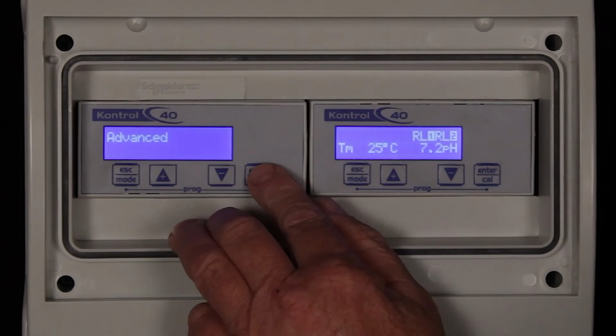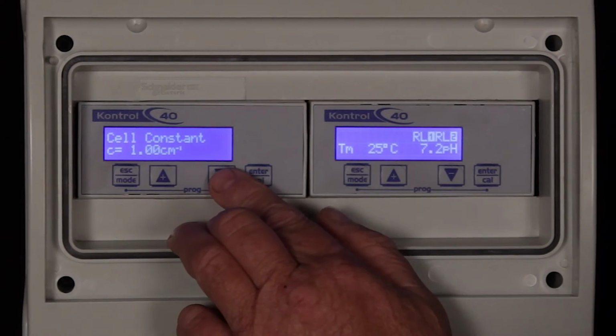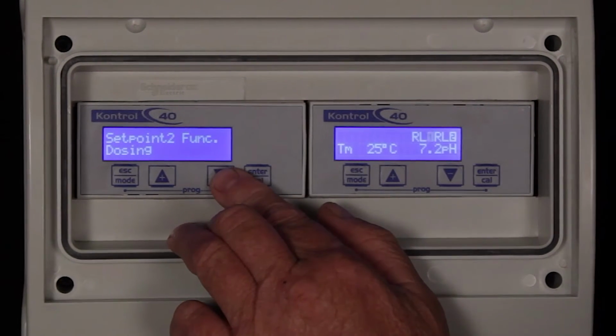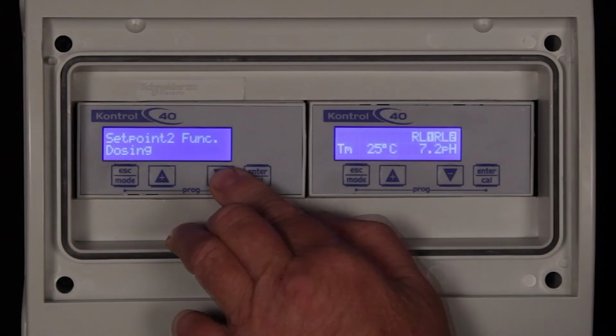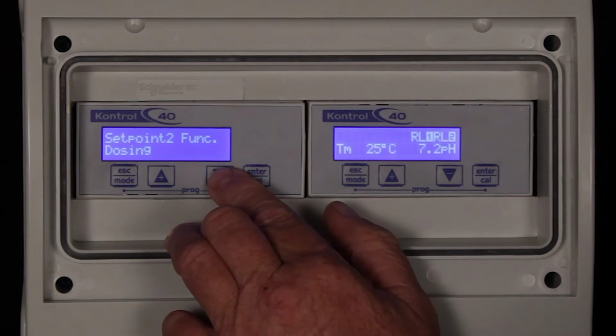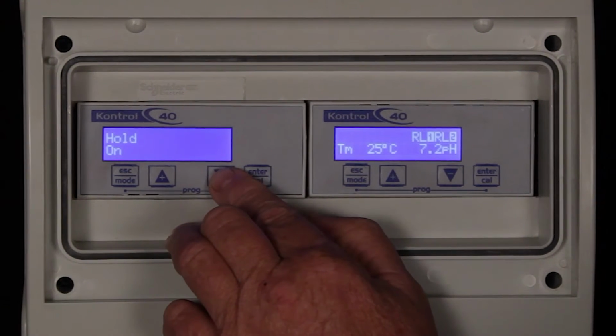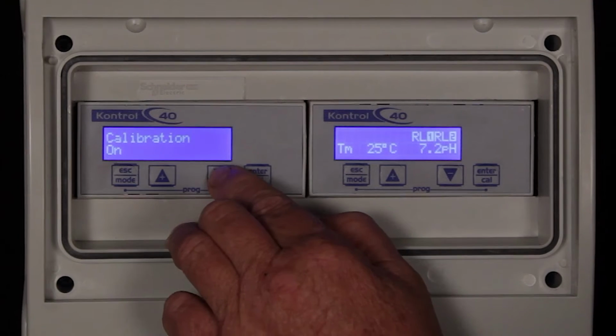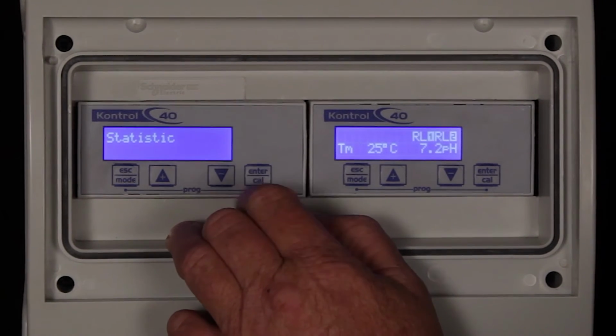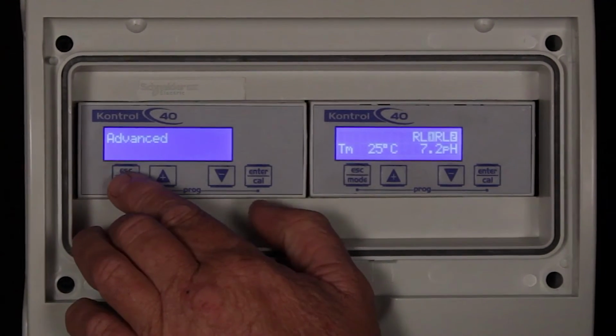In the advanced setting menus, the first value is the cell constant. The second value is for set point 2 function. It's important that this must remain on dosing for our application. The following parameters are hold on, calibrate on, and statistics. We do not need to change any of these settings for the purpose of our tutorial. For more information on what these settings do, please refer to the instruction manual.